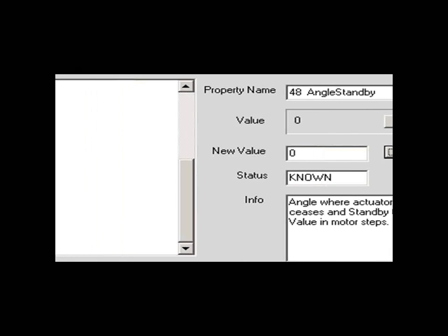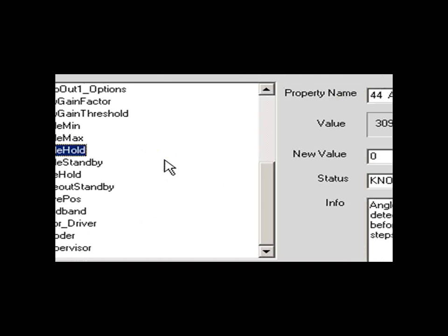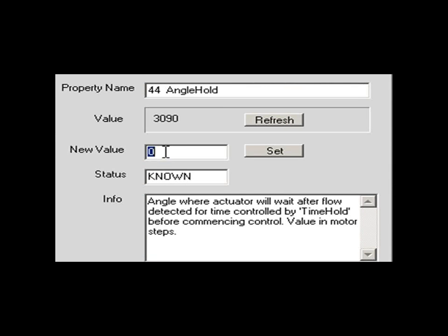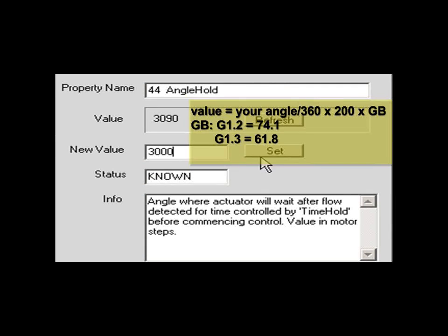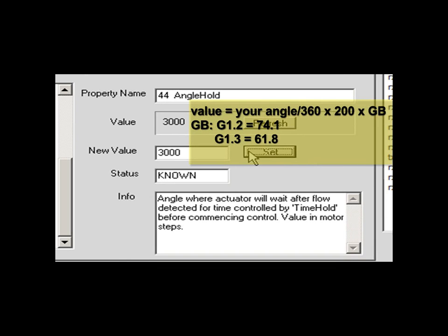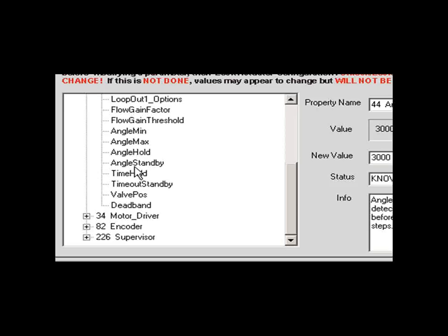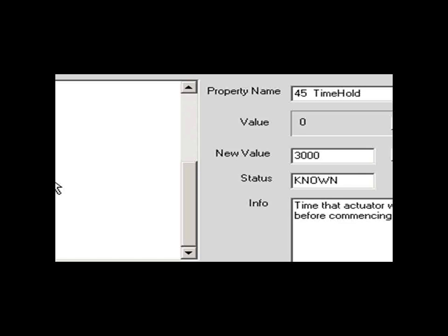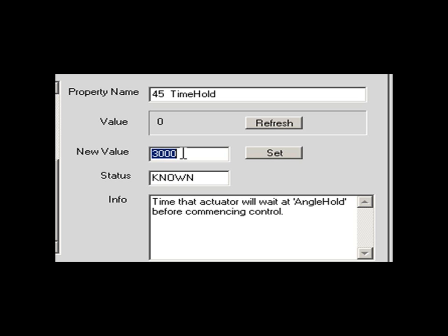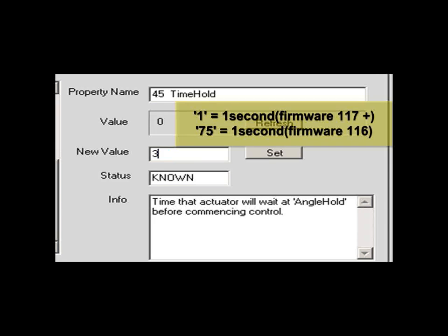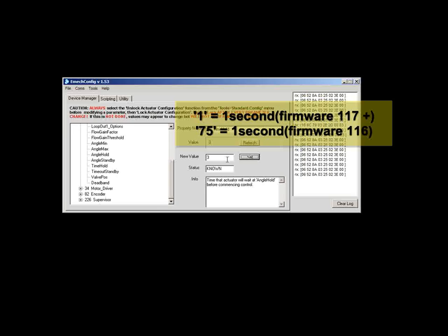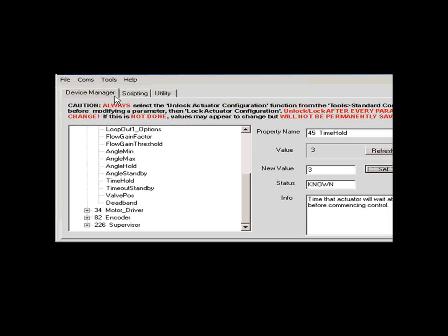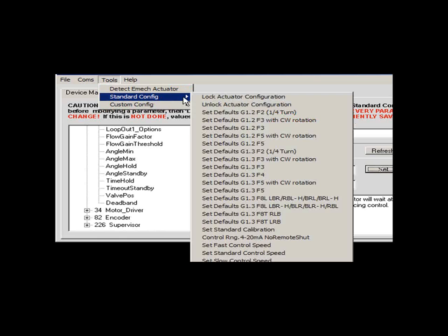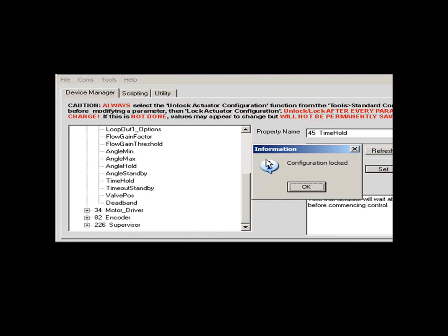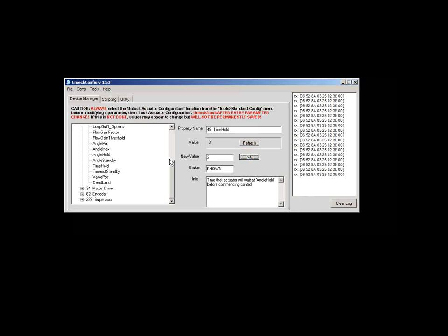Move to the left and select angle hold. In this example, I'm giving it a value of 3000, which is equivalent to about 88 degrees. Move to the left and select time hold. In this example, I'm giving it a value of 3 seconds. Finally, select Tools, Standard Config, Lock Actuator Configuration. The actuator is now set up so that the hold and standby features have been enabled.